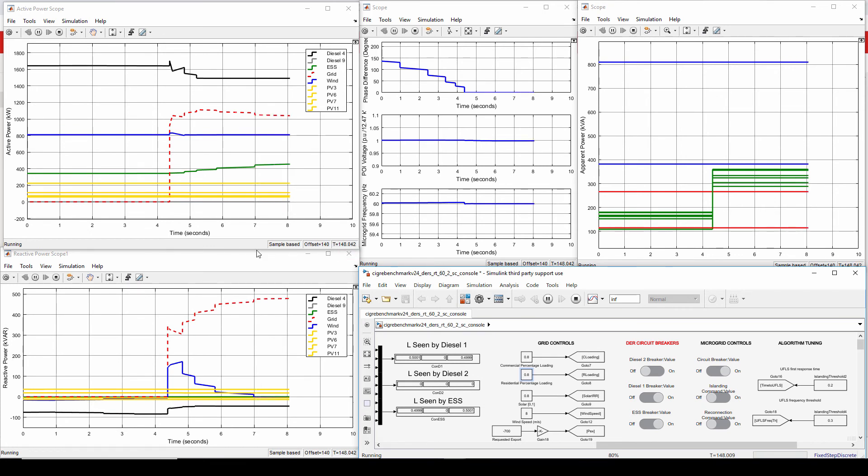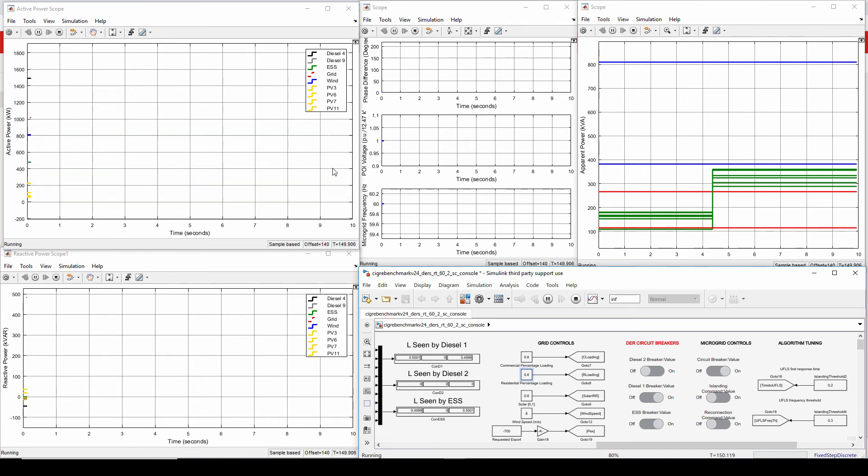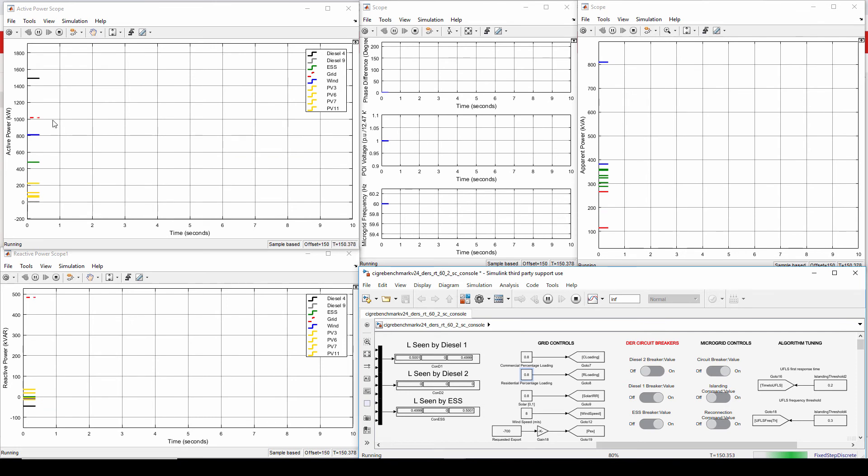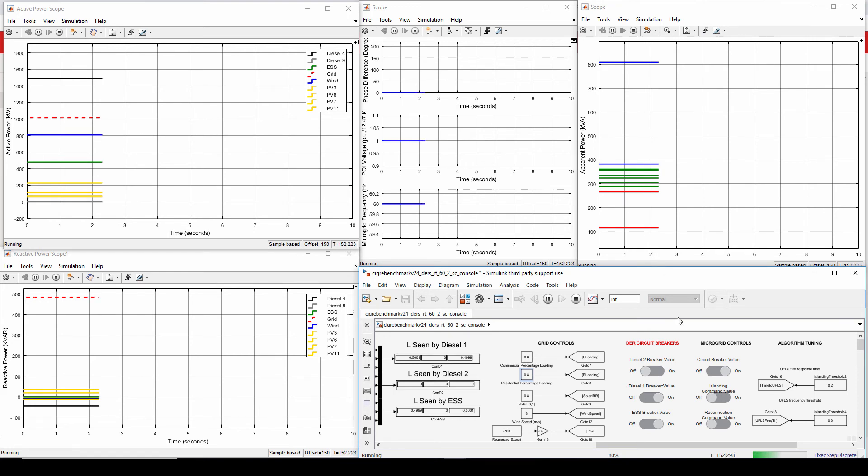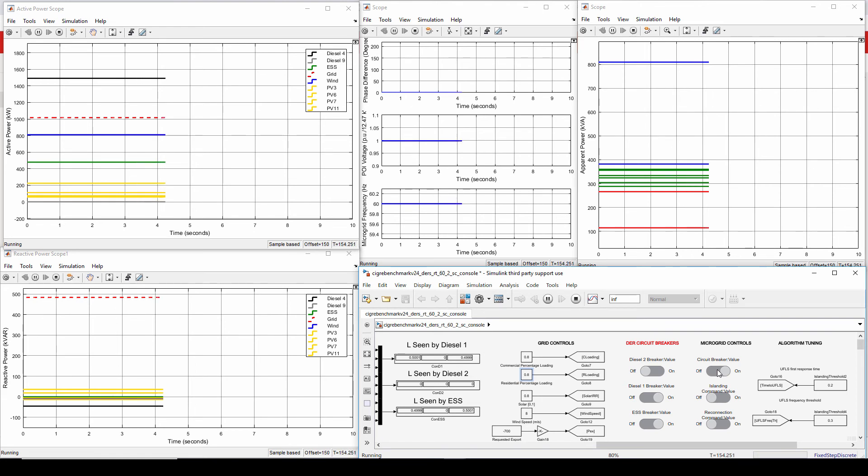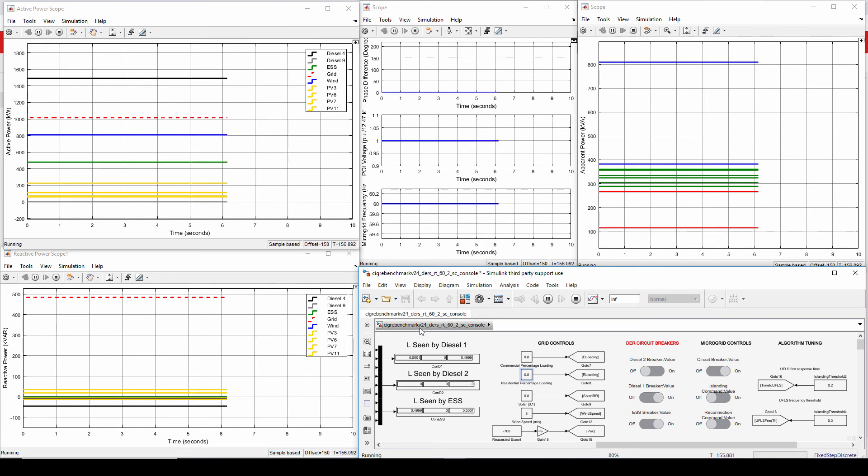Okay, so again, now back to where we started, the diesel and the ESS regulating the power at the POI. Now I'm going to issue unplanned islanding. Now for unplanned islanding, I'm going to trip the circuit breaker of the microgrid and I'm going to do that without requesting an islanding request. So there wouldn't be intentional load shedding specifically for islanding. So what will happen is it's like an emergency dispatch mode. Under frequency load shedding will need to occur. And for that, an algorithm is being employed that is other than the consensus algorithm.